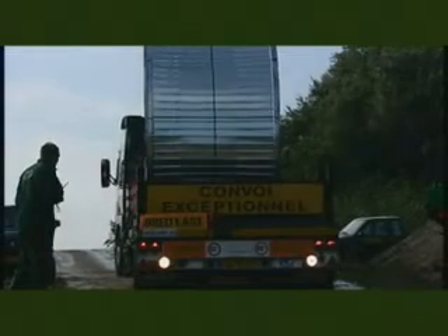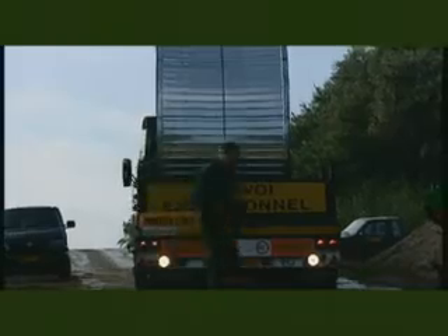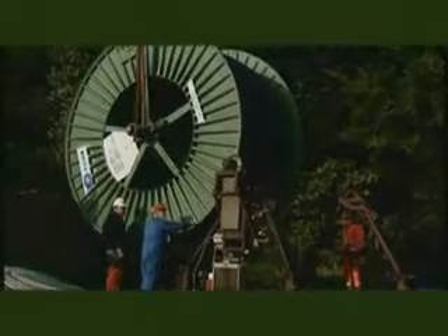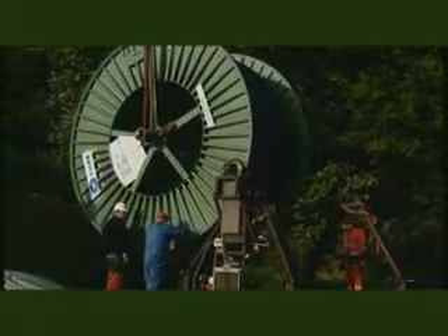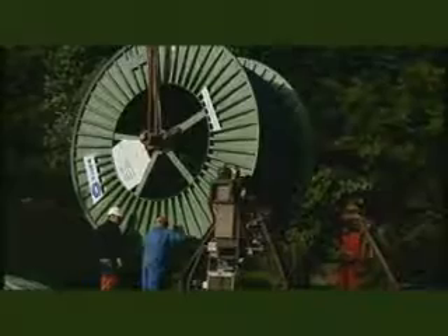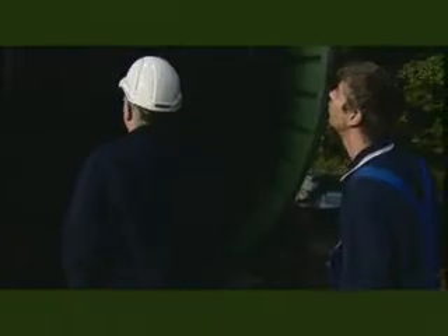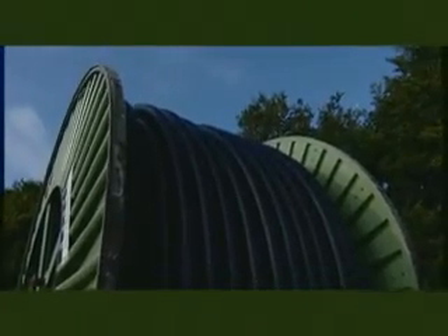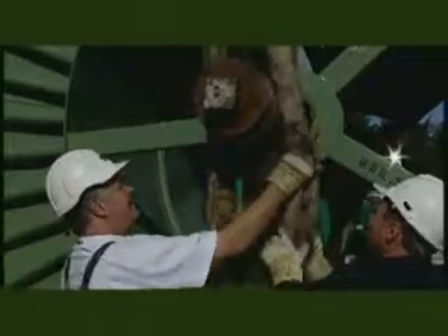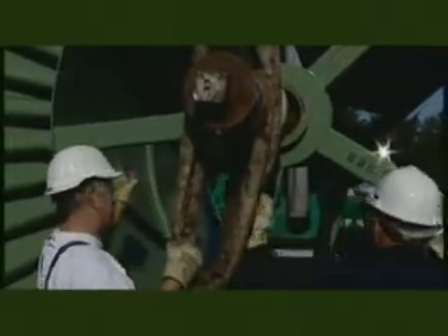The submarine cable is significantly heavier than the land cable as it is protected with a lead sheath instead of an aluminium sheath. A drum with a 900-metre submarine cable weighs approximately 24 tons. Each drum has a diameter of 4.2 metres and is 2 metres wide.